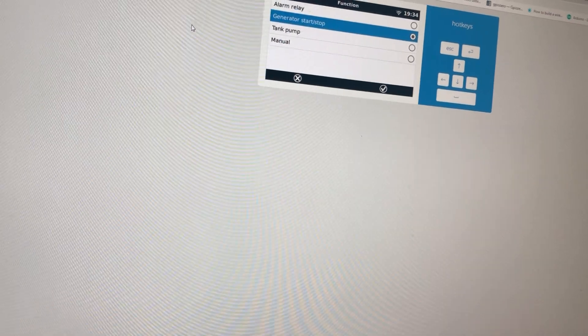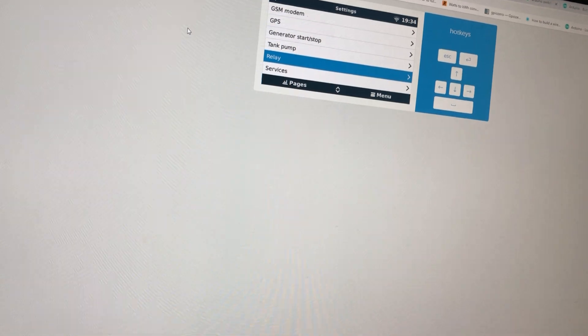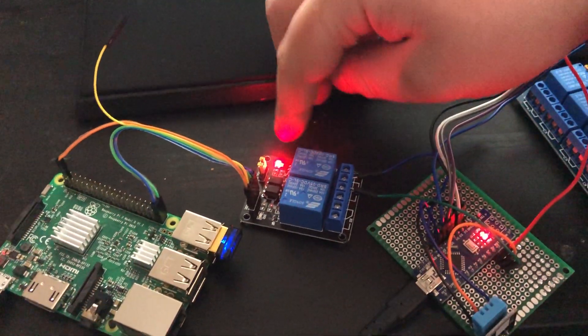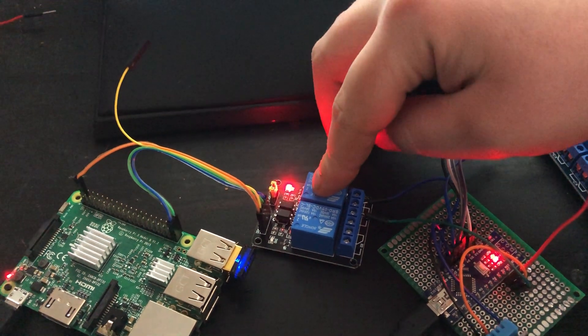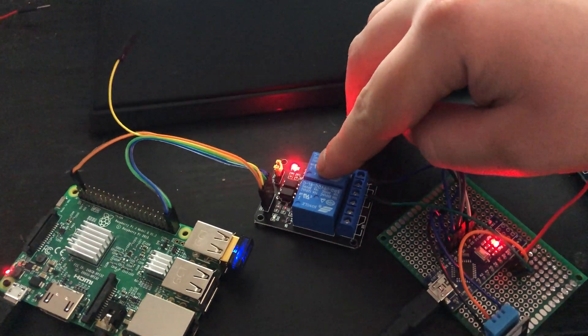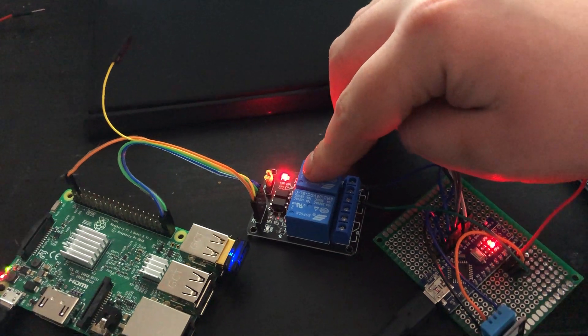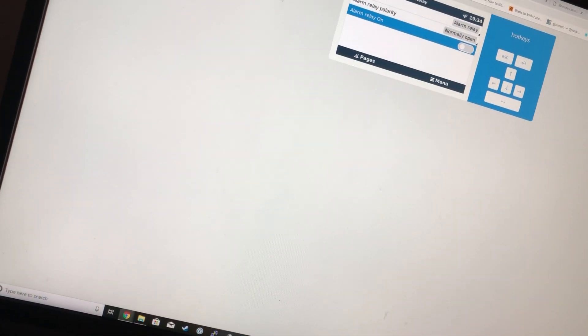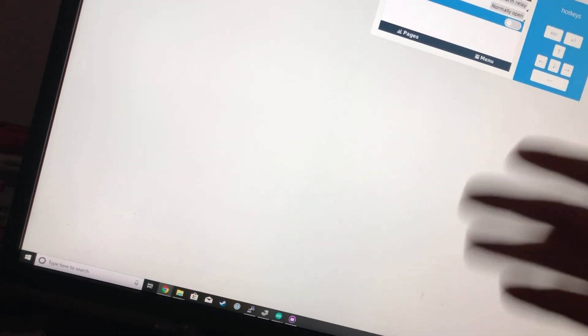I'll go into relay. And I'll just set this to be an alarm relay so I can control it manually. So right now there's no alarm and the generator is not supposed to be running. I'm going to trigger, let's say my battery drops down to a low charge that I configured for the generator to kick on, or I turned on my air conditioning and it's running for more than 20 seconds.